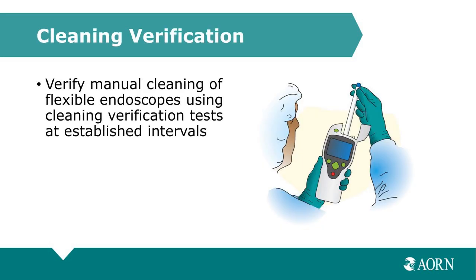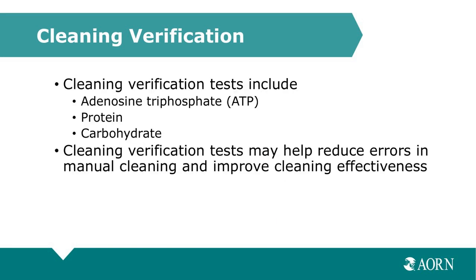AORN recommends that manual cleaning and inspection of flexible endoscopes is verified using cleaning verification tests at established intervals, such as after each use or once daily, and also whenever new endoscopes are purchased. Your cleaning verification tests include adenosine triphosphate, or ATP, and there are also chemical reagent tests available for detecting clinically relevant soils, such as protein or carbohydrate. Periodic verification of the cleaning effectiveness can help to reduce errors in manual cleaning and improve the effectiveness of cleaning.